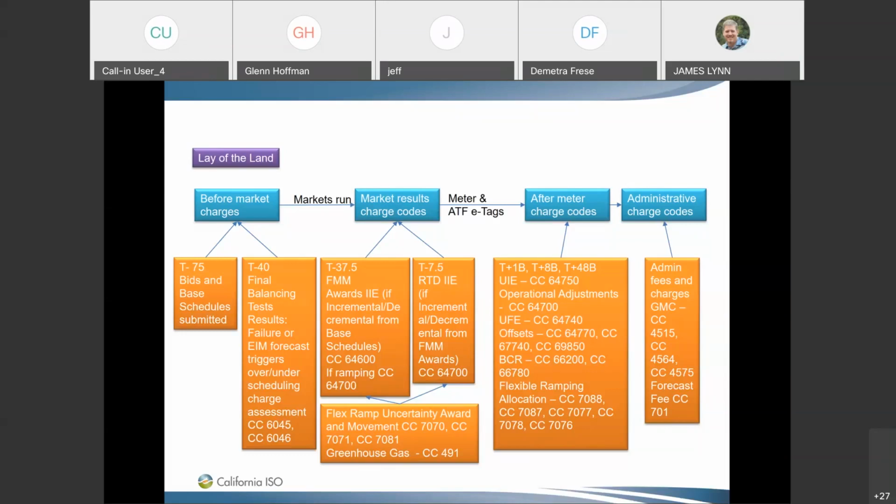Now, if we've limited the direction in which you can provide transfer capability, we limit the ability for your resources to provide flexible ramp awards to solve the EIM area requirement. So for most cases, and it doesn't always occur, if you fail the flexible ramp up, your resources are primarily going to be used to meet your need, and unless you have transfer out capability, it's not going to meet any of the EIM area need.